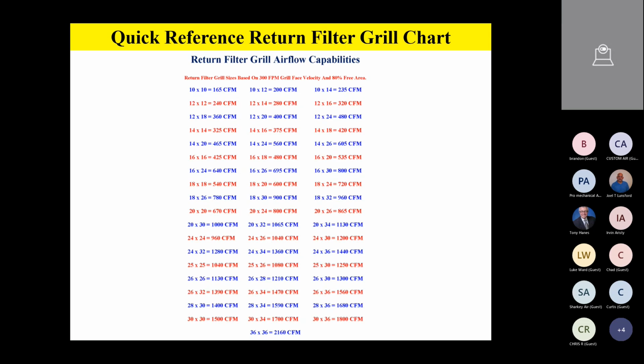Yeah, I got one. So we use our chart and find out that we have higher than desired static pressure. It drops our CFM below the 400 CFM per ton rule. Is that going to have an effect on capacity or efficiency or both? Oh my God, that is an absolutely excellent, timely question, and the answer is yes to both.